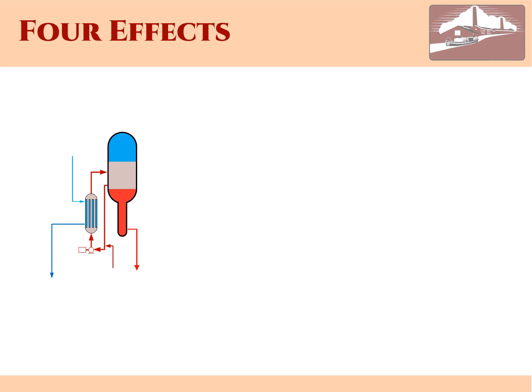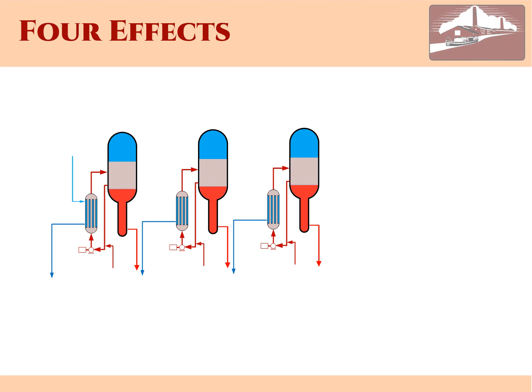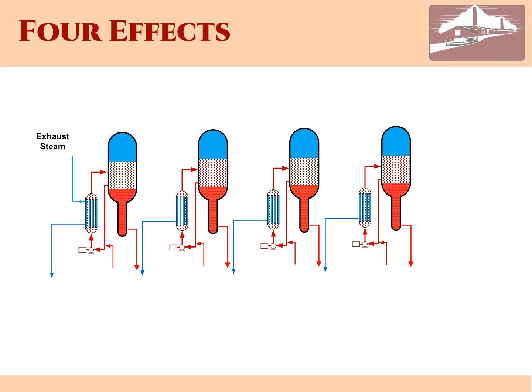Each evaporator vessel is known as an effect. Hence, a plant with 4 vessels is known as a quadruple effect evaporator. The first effect is heated by exhaust steam from the turbines in the powerhouse, which arrives at a temperature of 126 degrees C, and heats the brine to 103 degrees C. If the pressure in the vessel is maintained at 1.12 bars, the brine will boil at 103 degrees C, and the vapour can be drawn off through the second calandria.